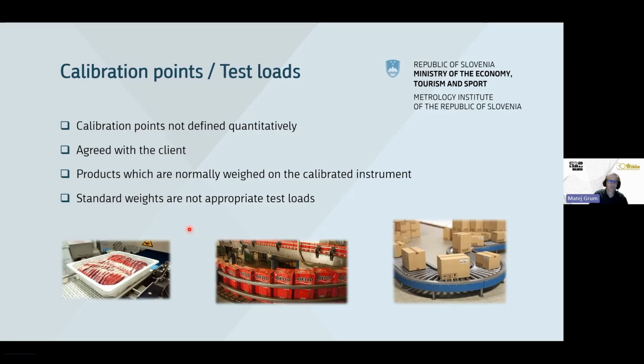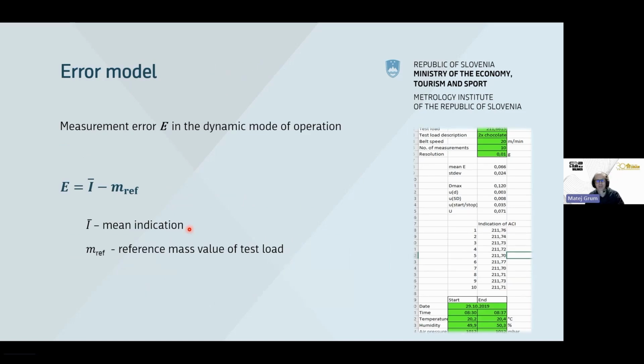But the most important is the test loads and calibration points are defined by the product, which are normally weighed on the instrument. The calibration process itself can be very well explained through the error model, which is used in the guide to evaluate the error of the instrument and then to evaluate the uncertainty of the measurement. Basically, the error model is simple. On one side, we have a test load where the reference mass needs to be defined. On the other side, we have the response of the instrument, represented by the mean indication. And the difference between those two is the error of the instrument in the dynamic mode of operation.